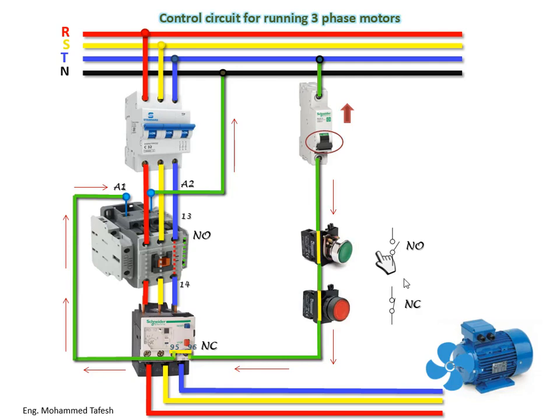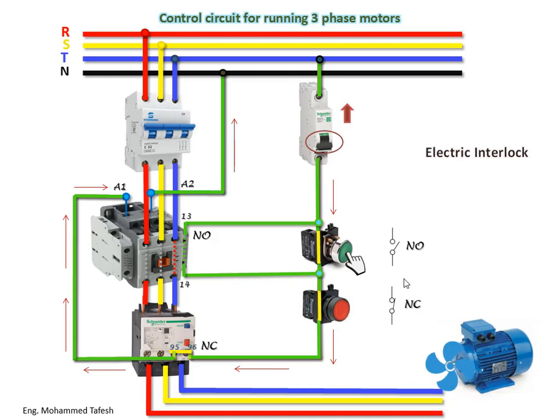The solution to keep the circuit running even after releasing the push button ON is the electric interlock — a lock between the contacts of the start button and the auxiliary contacts 13 and 14 of the contactor. While pressing the push button ON, the electric current passes through the switch and the rest of the control circuit. As soon as I take my finger off the button, the current will still pass through the interlock path via contact points 13 and 14.